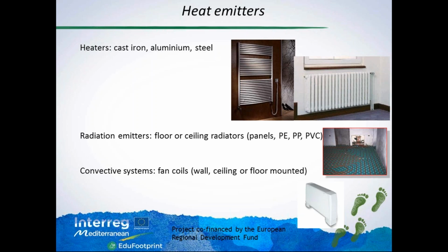And at the opposite, we have radiator panels, floor panels. They can be mounted also on the ceiling or behind the wall, behind the plaster. But those are using the radiation kind of heat transfer. They heat the wall element, the building element, and the floor or the ceiling are re-emitting heating radiation into the room.